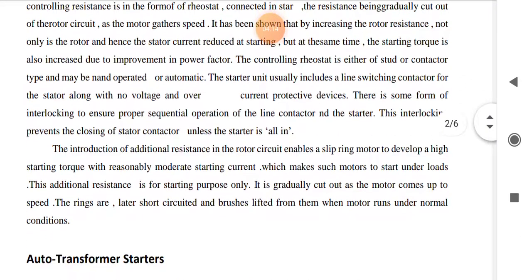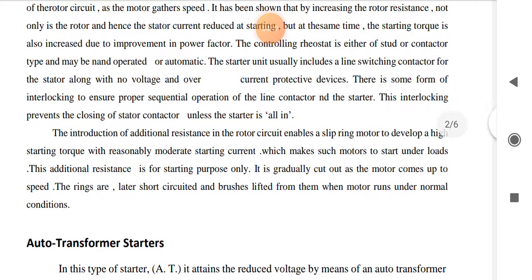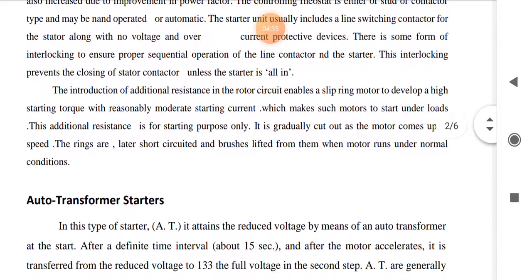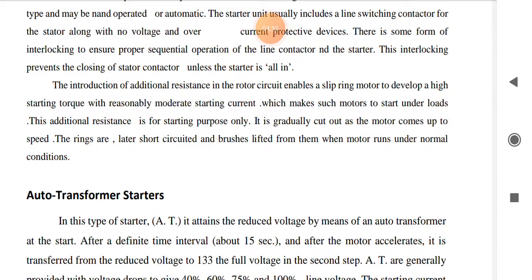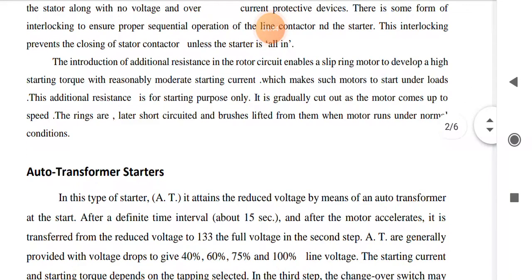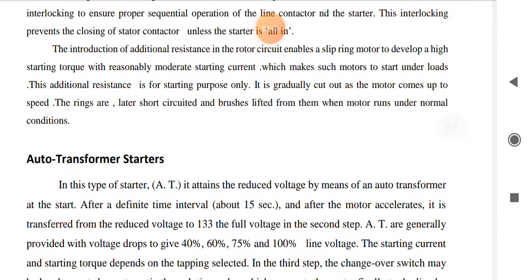The controlling rheostat is either of stud or contactor type and may be hand operated, semi-automatic, or automatic. The starter unit usually includes a line switching contactor for the stator along with no voltage and over current protective devices. There is some form of interlocking to ensure proper sequential operation of the line contactor and the starter. This interlocking prevents the closing of the stator contactor unless the starter is all in.